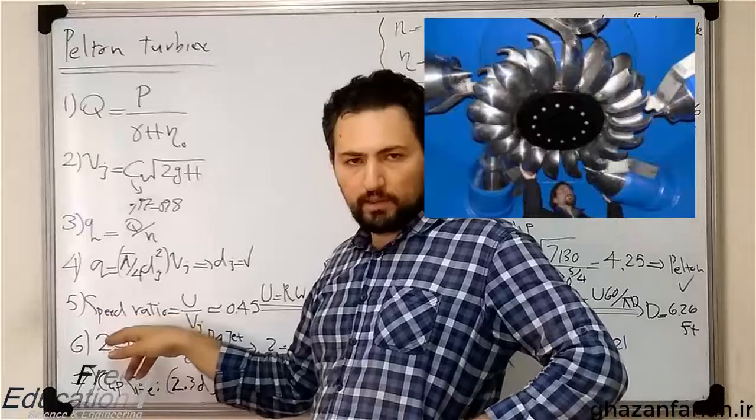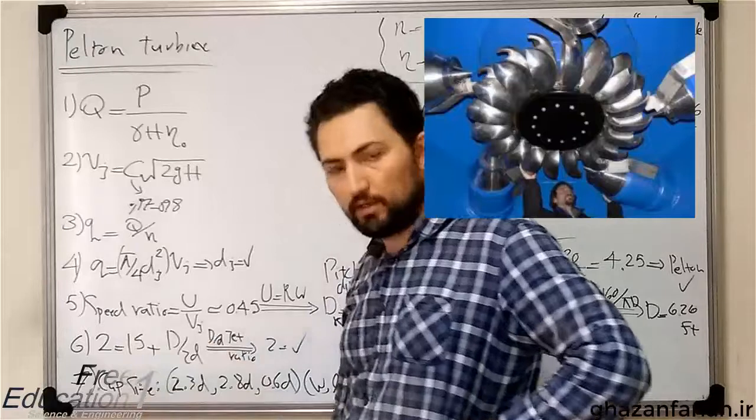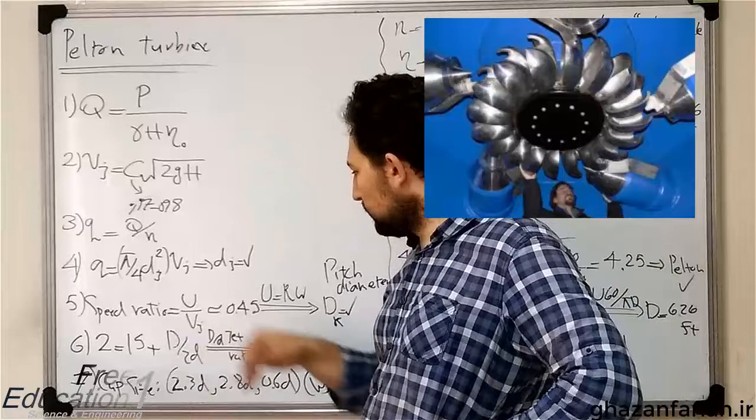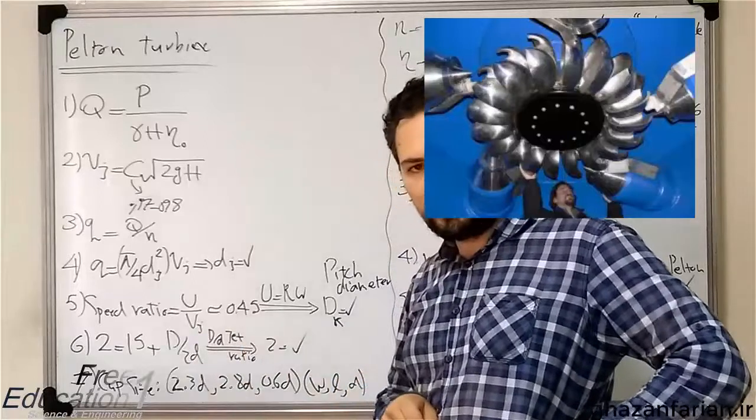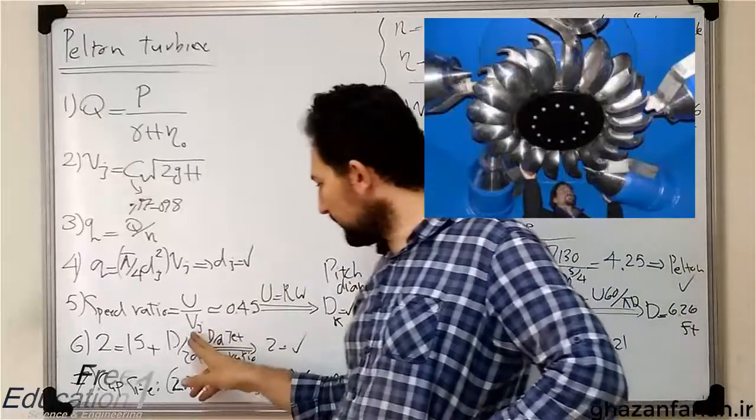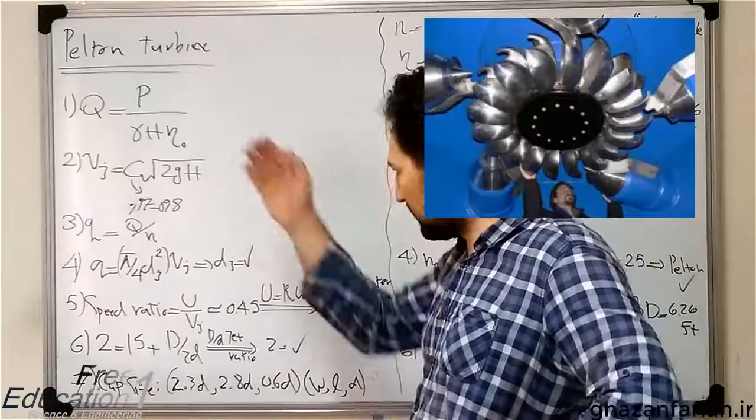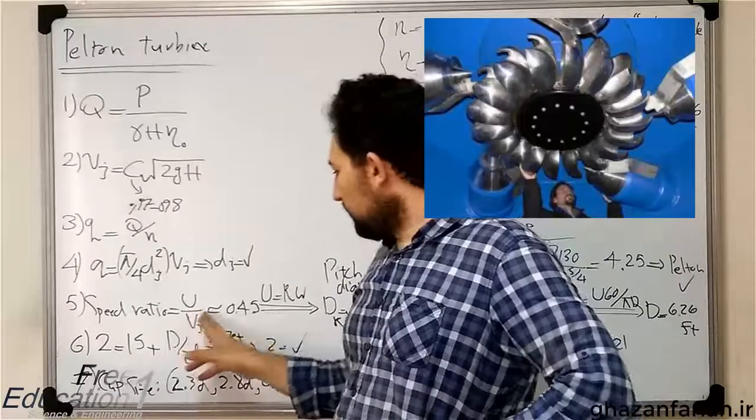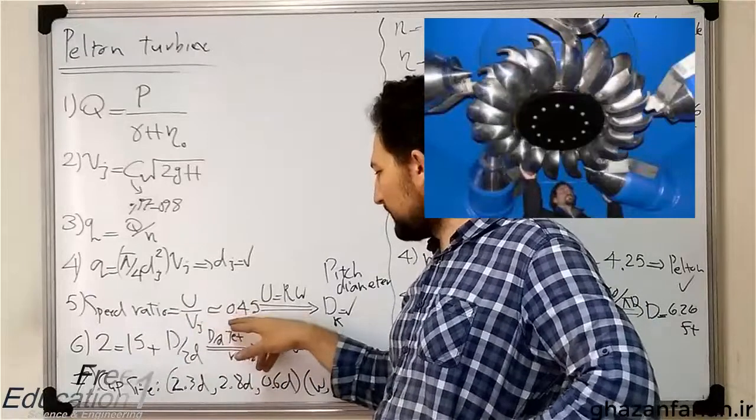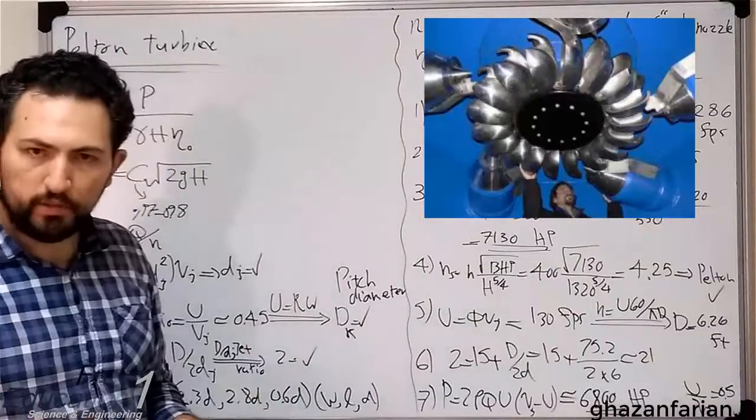We have another relation or another parameter in Pelton turbine, which is the specific speed ratio, which is the ratio of two speeds. The numerator of this relation is the circumferential velocity of the runner, and the denominator is the jet velocity. Again, using the result of step 2. So, this speed ratio is recommended to be approximately equal to 0.45. There is one extra point here.